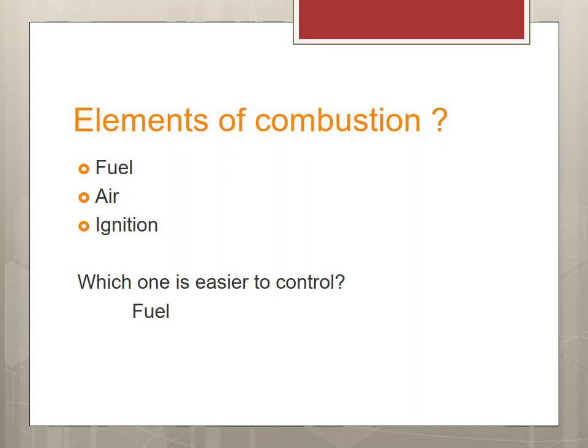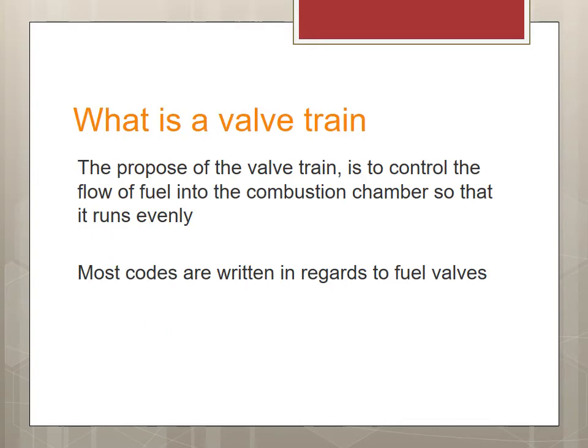Think about your car — you always control the gas. So what is a valve train? It's a train made out of valves, one after another, going in line in series, because there are safety and control elements. The purpose is controlling the fuel going into the combustion chamber, regulating the amount of fuel, and also acting as a safety device to shut off the fuel whenever something goes out of bounds.